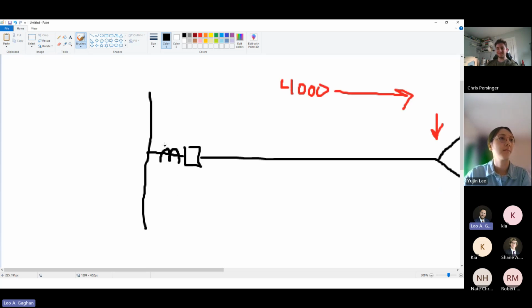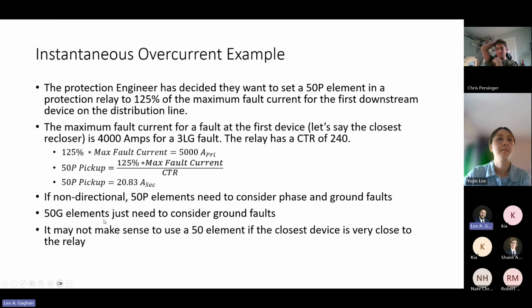So we've got that CT that we talked about in previous classes. It'll be, let's say, 1,200 to 5, which is that 240 that we talked about. So it'll take that 4,000 amps and reduce it down to a smaller value for our relay, a value that's not going to blow our relay to shreds, essentially. But when you pick your setting, it's based off that smaller value, because that's what the relay is actually seeing. So that's why we're doing that.